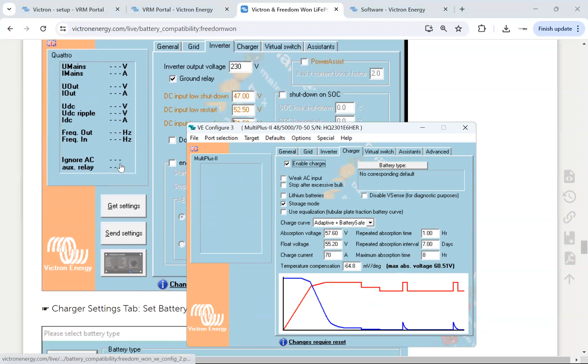So let's go to charger. We can scroll down on the web page again, and we go to the charger settings tab, right? So you click on the battery type. And I've already put in Freedom 1, but I'm going to follow through. Click on lithium iron phosphate there, click OK. It says it's automatically changed the settings. Click OK. Now, what we need to do is set the absorption voltage to 55.8 and the float voltage to 55.8. So we're going to click on that, go 55.8, and that 55.8.